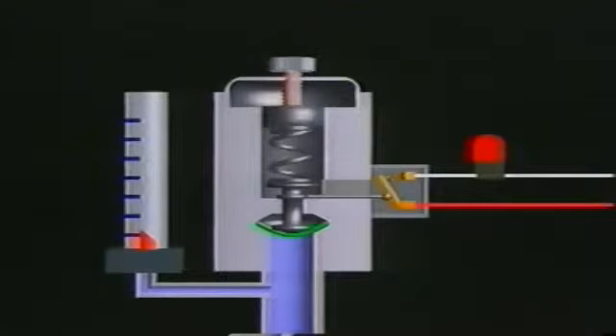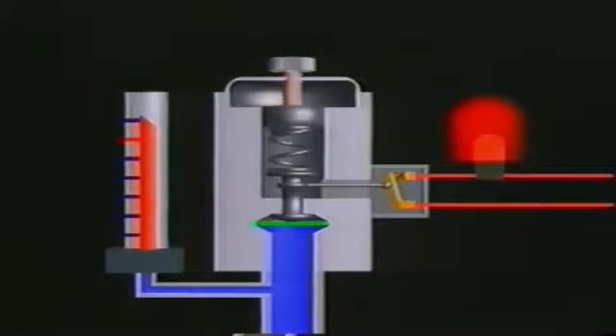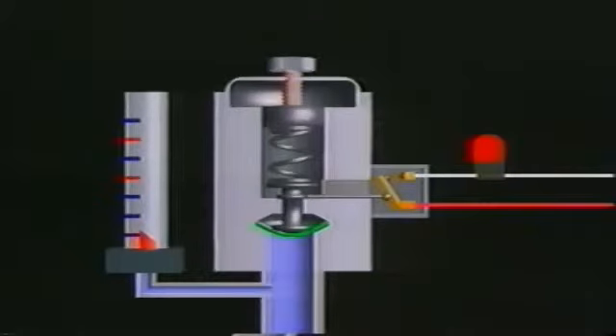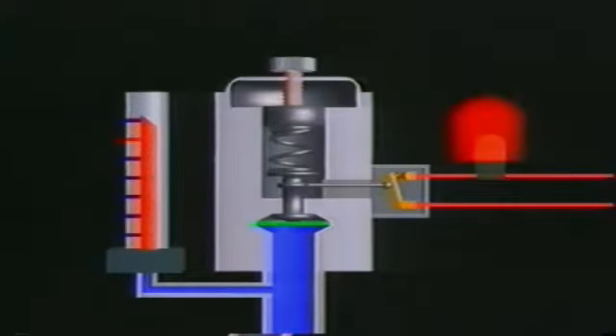And here is how it works. The pressure is exerted on a diaphragm or a piston. When an adjustable preset pressure is reached, a micro switch is actuated which closes the circuit, thus generating an electrical signal. If the pressure drops, the switch automatically opens again at a certain pressure. The difference between the switch on point and the switch off point is the hysteresis of the pressure switch. This varies according to the pressure range. The hysteresis is caused by the frictional resistance in the components of the switch. It is important to know the hysteresis of a switch because it switches at different points for rising or falling pressure.